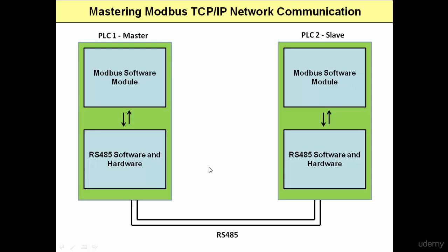So that is a very important distinction there. It's why Modbus software is really what you call hardware independent or communications mechanism independent. Modbus software just defines the arrangement of data. It doesn't define how the data is transported. Very, very important point, big idea. So that separation allows Modbus to use different types of hardware and communication mechanisms to get its data across, because it doesn't depend on one type. It's separated. It doesn't define the type.